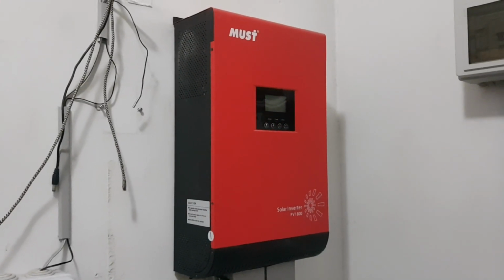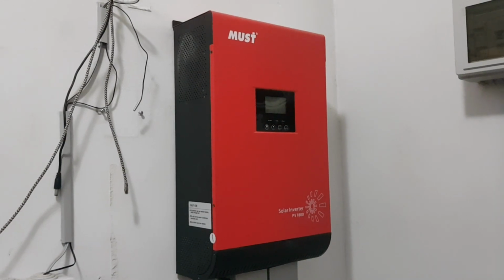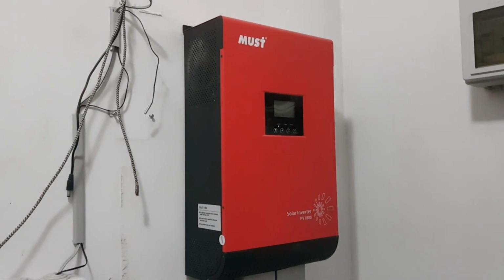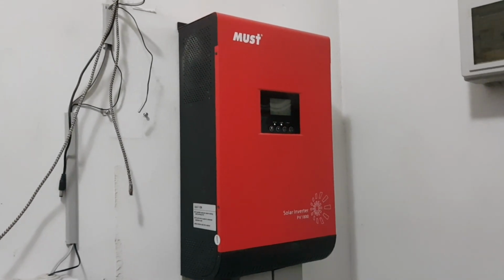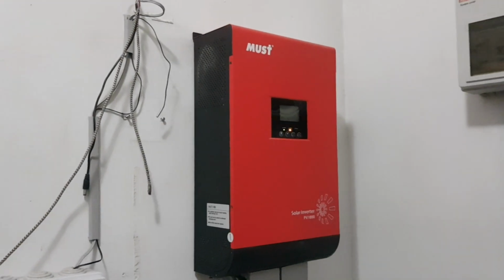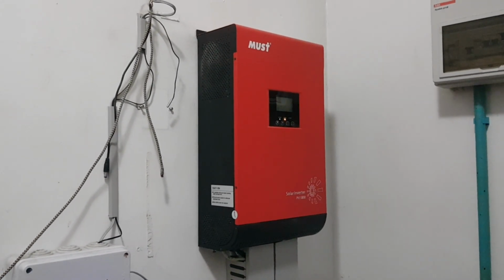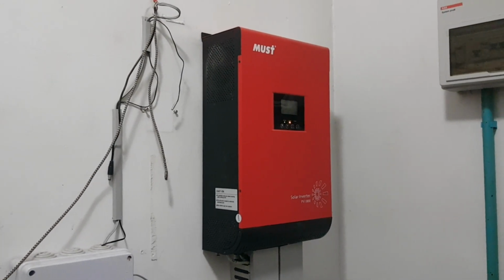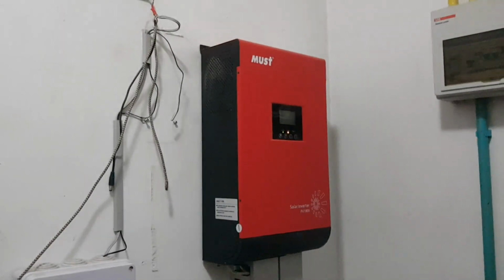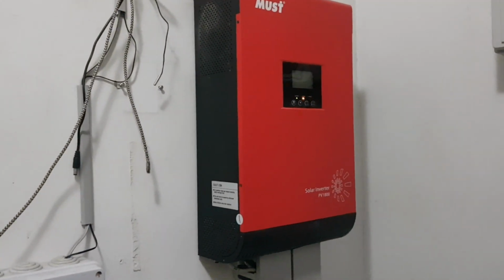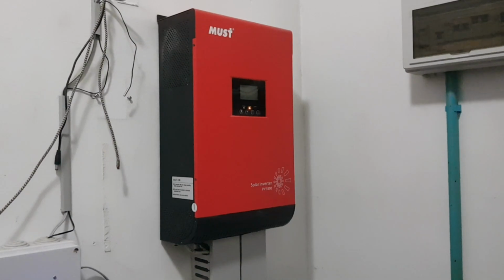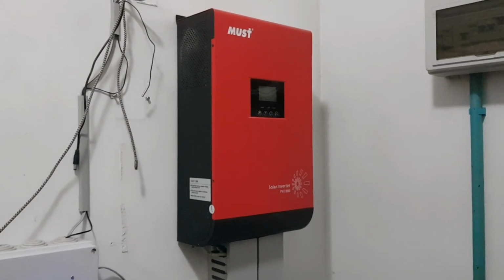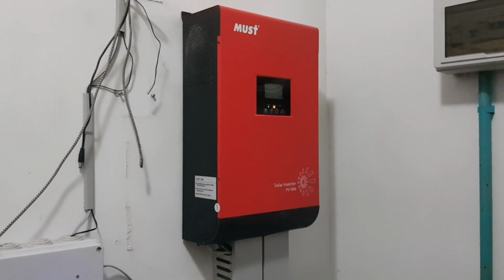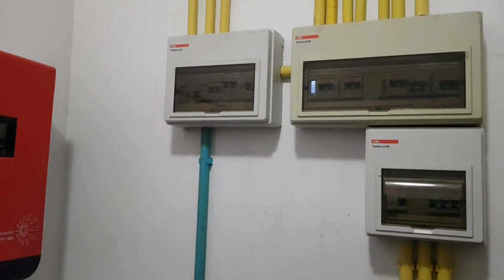So if you have an all-in-one inverter like this one, the only contact this is providing is a so-called dry contact. But the dry contact does not necessarily tell anything about the mode or the state of where this inverter is right now connected. So if it's running from the battery, if it's off-grid, or if the so-called grid bypass is activated. The only thing a dry contact tells is more or less the state of charge of the battery. And the only mode where this would kind of be similar is that when the state of charge goes down below a certain level, the inverter would then automatically switch over to the grid, right, where it gets the power from.